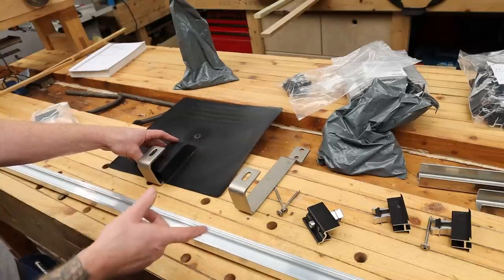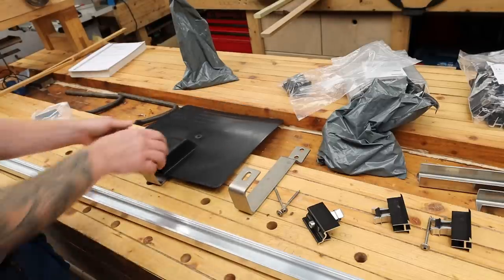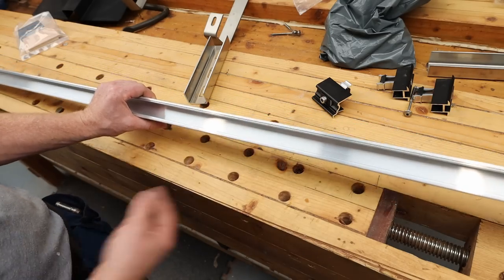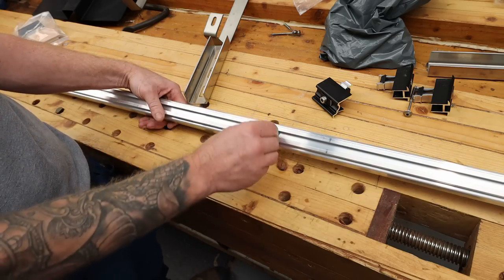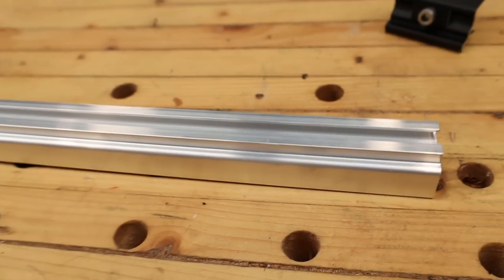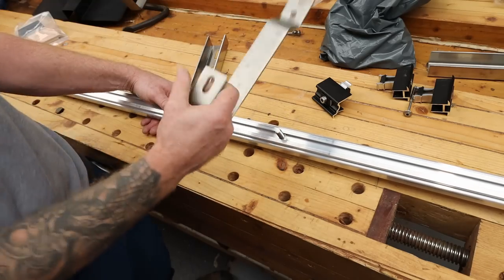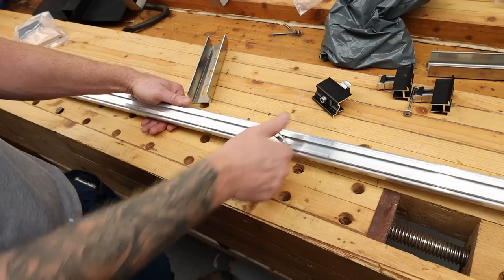Once you get all your brackets in place, you fit on your aluminium rails — this is what your panels will bolt to. The main piece of aluminium rail has a T-track on the back. You get a couple of T-bolts that click in, and you bolt this to your bracket sticking out of your roof, making sure you have enough supports so everything is nice and supported.